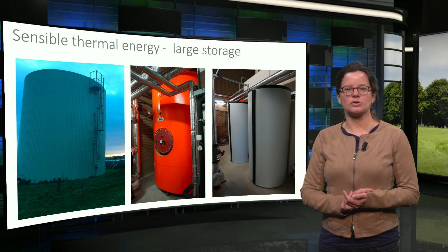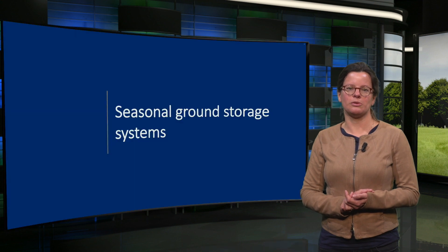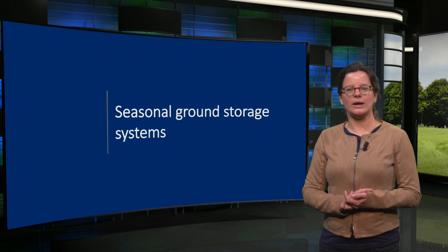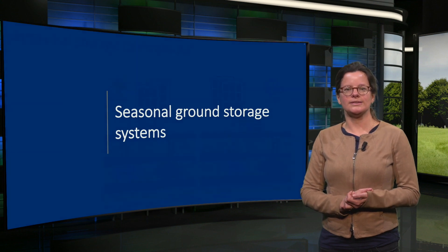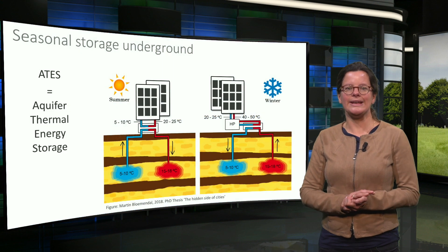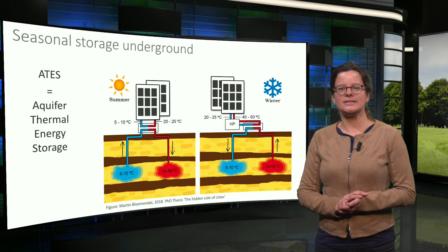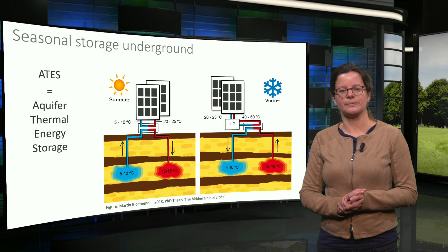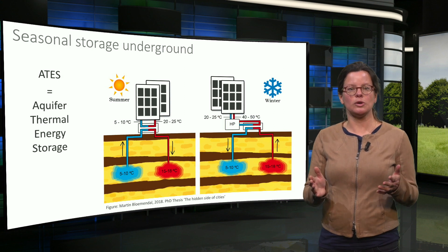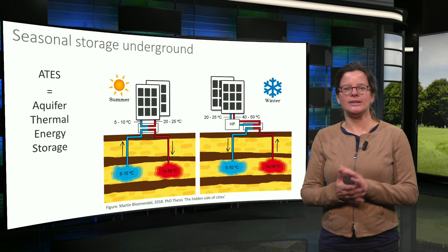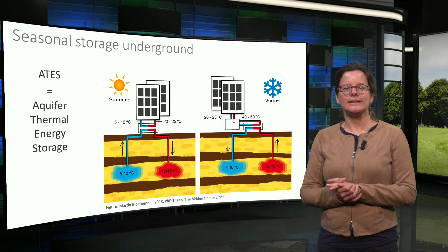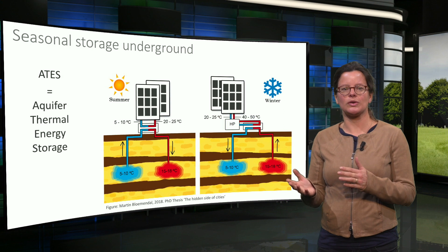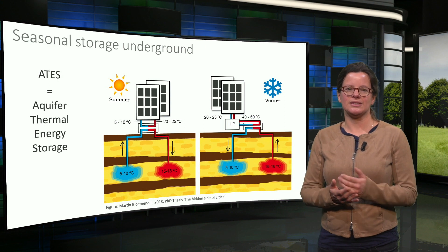Therefore, the subsurface is often used for seasonal thermal energy storage. Subsurface aquifers — underground layers of sand with groundwater — can be used to store heat. These systems are called ATES systems: aquifer thermal energy storage. In these systems two wells are drilled, which will become a cold well and a warm well. In summer, groundwater is extracted from the cold well. It passes through a heat exchanger in order to cool a building. The heat from the building is transferred to the groundwater, which is then injected into the warm well.